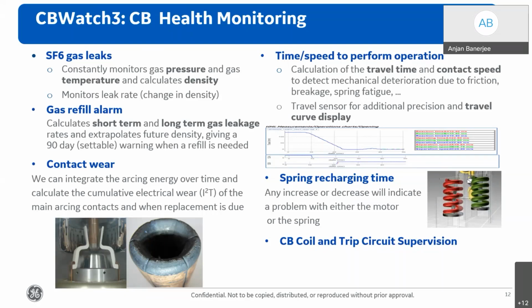Further, the device also monitors the health of the closing coil and the tripping coil by monitoring the coil current. The device also supervises whether there is any issue with trip circuit integrity, and if there is any trip circuit opening, the device would generate an alarm. So that means each and every component of the circuit breaker is being monitored by this intelligent electronic device known as CB Watch, offered by GE.